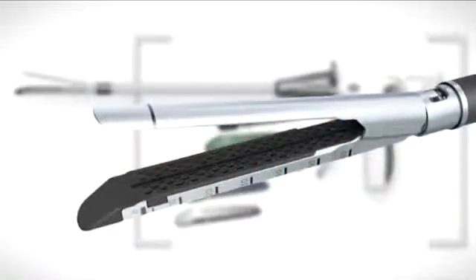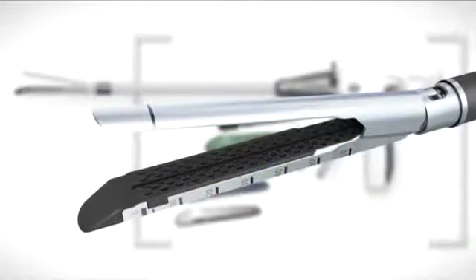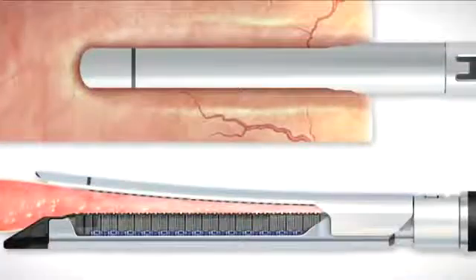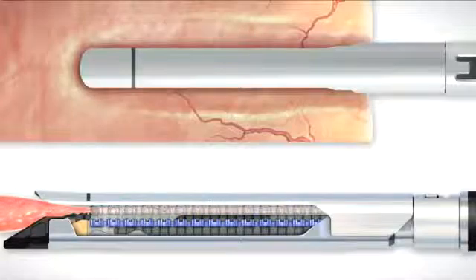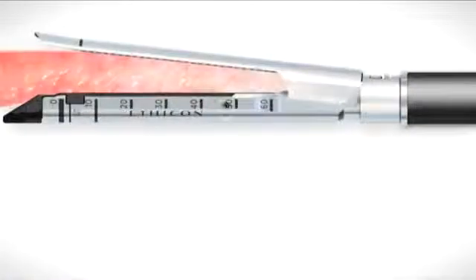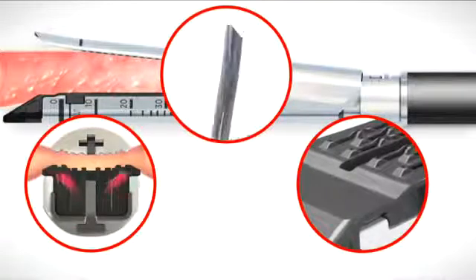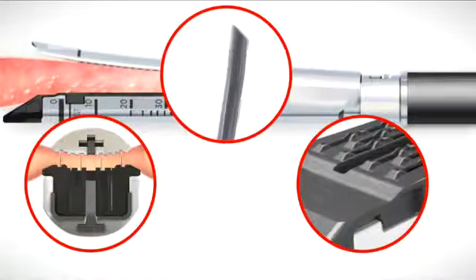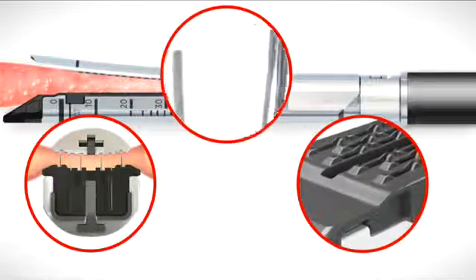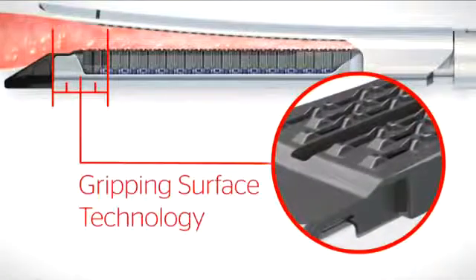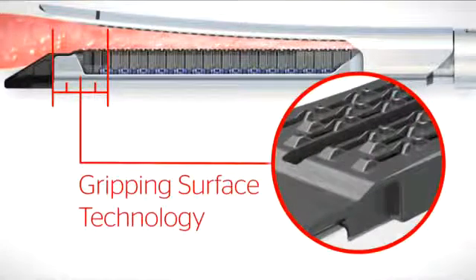To deliver the next step in the evolution of stapling technology, we recognize that for optimal stapling performance, it is critical to control the movement of tissue during the stapling process. This GST system incorporates three major design elements to reduce tissue slippage or movement while delivering reliable staple formation and precise tissue transection across a broad range of tissue thicknesses with each reload.